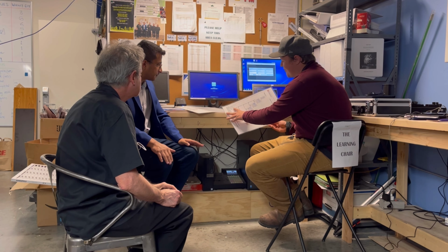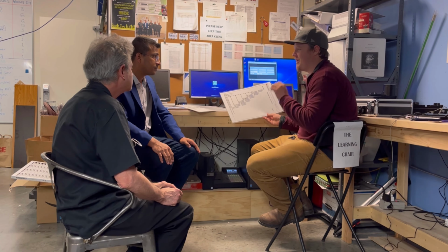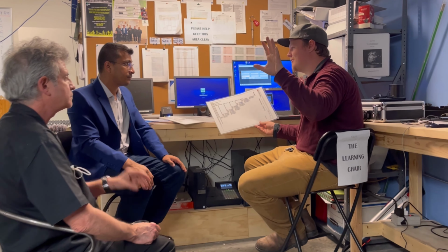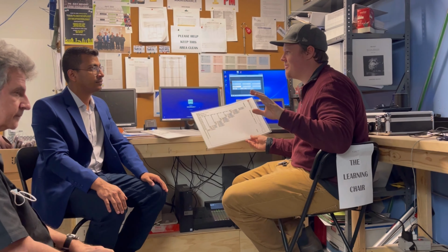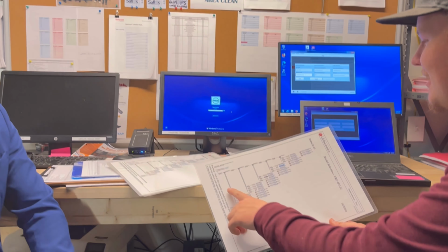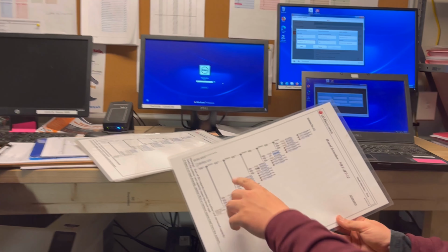So you have your additional refrigerant charge, and then you'll have the nameplate data on the system itself. If you look at the nameplate of the condensing unit, it should have the factory charge that was provided, and you would need to add this additional charge on top of that, right?